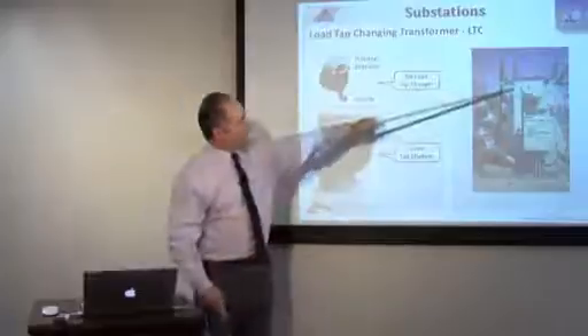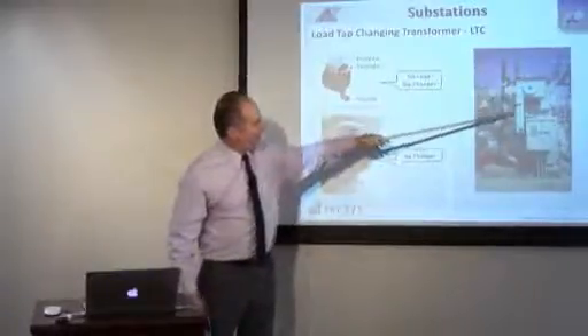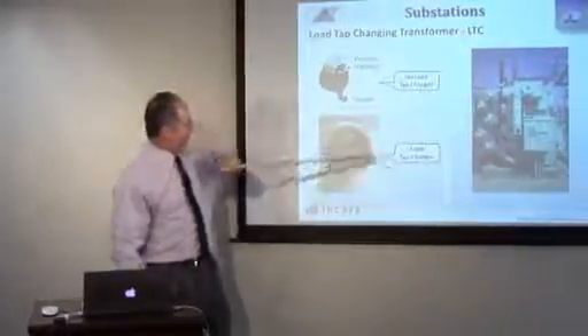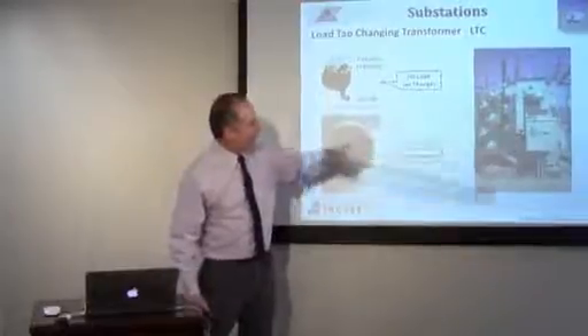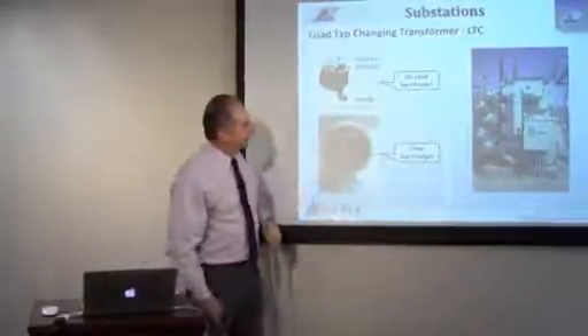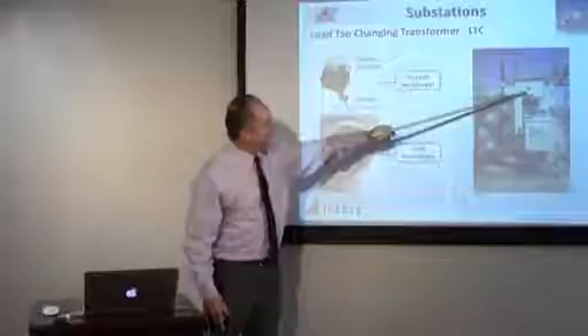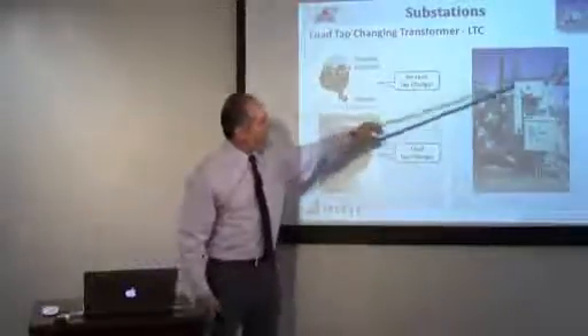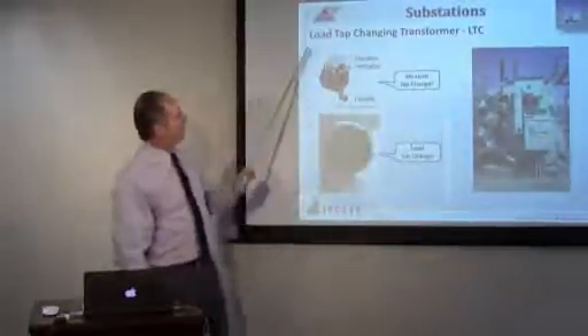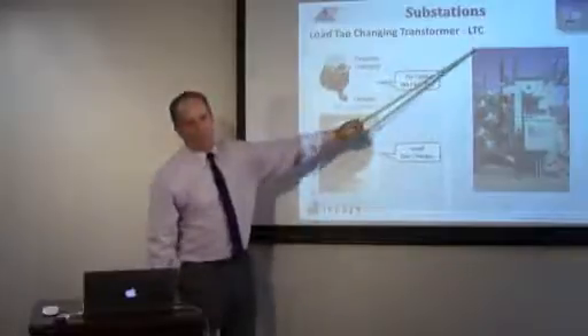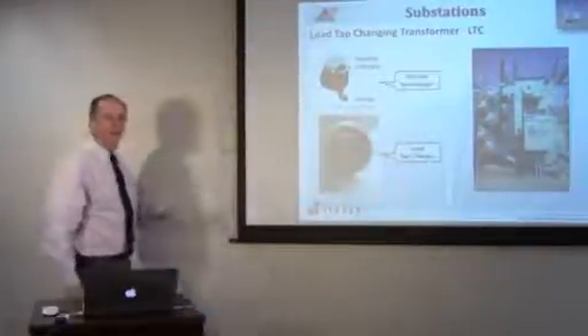So in this picture you have a regulator. There's the gauge. This gauge right here is right down here so you can see what it is. And then there's a transformer and a regulator. When they're both together, transformer and a regulator, they're called a load tap changing transformer, or LTC. And you'll see a lot of LTC transformers in substations.